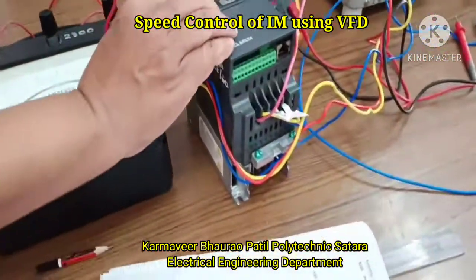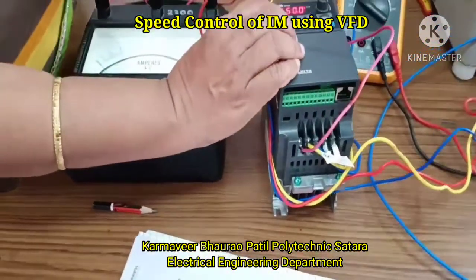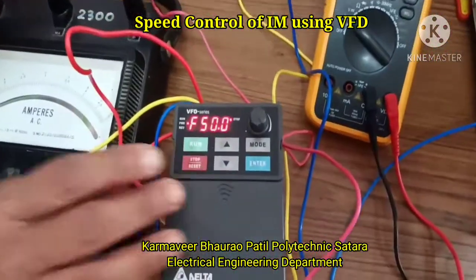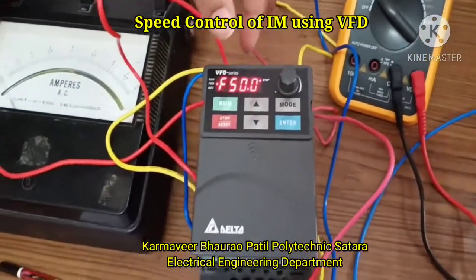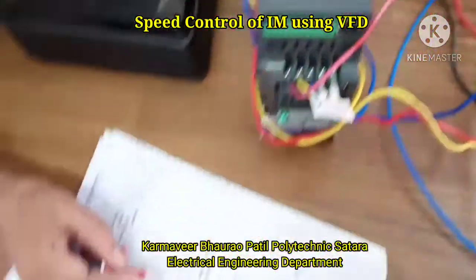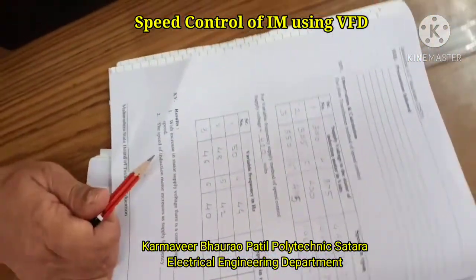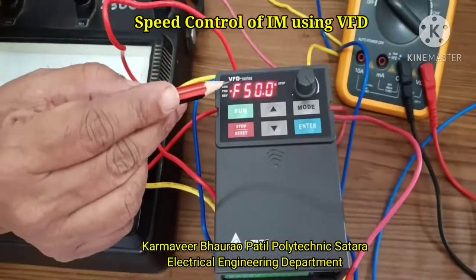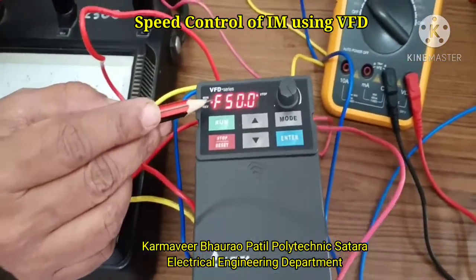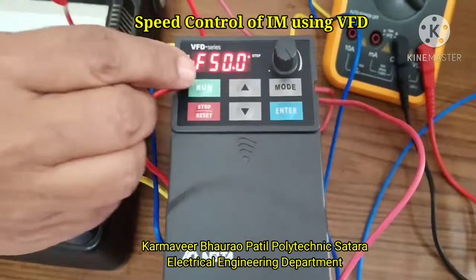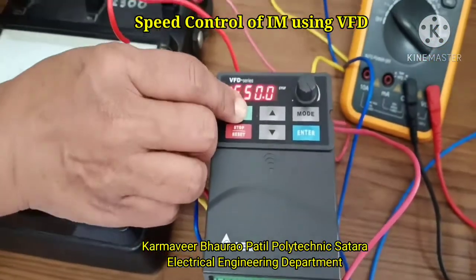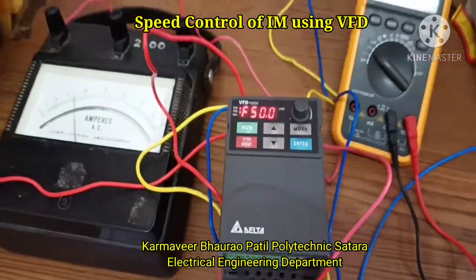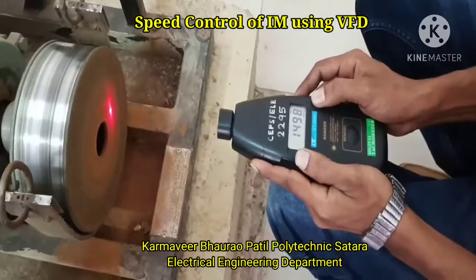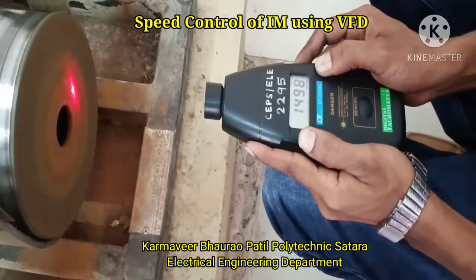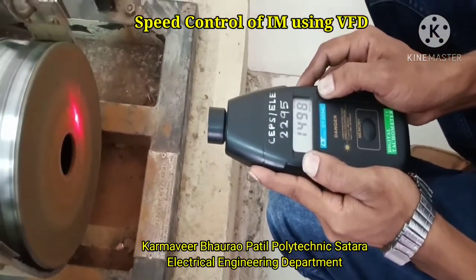Now to start the motor, first we will press the reset button. Okay. And now we are going to start the motor. At present, how much is the frequency? Frequency is 50 hertz. When you press the run button, the motor will start. I have selected which mode? Forward direction and measurement of frequency. So I will press this button and you will see that because you have given a rated voltage and the normal frequency.